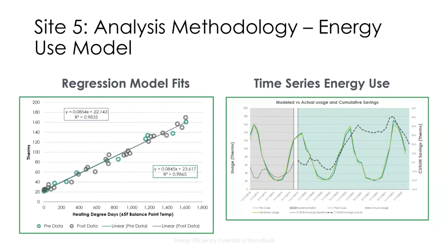The graph on the right shows a time series of energy use. We modeled the baseline, which was water. So on the gray side, we're comparing this modeled baseline with the actual baseline, the actual bills, which in theory should always be close. And then after a break for the nanofluid installation, we get to the green side where we compared our modeled baseline with the billed consumption. And then the difference between those two green lines in the chart shows the cumulative energy savings across that whole period, which is represented in the dotted line.